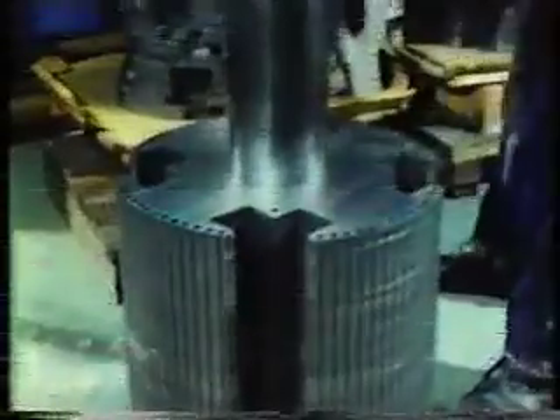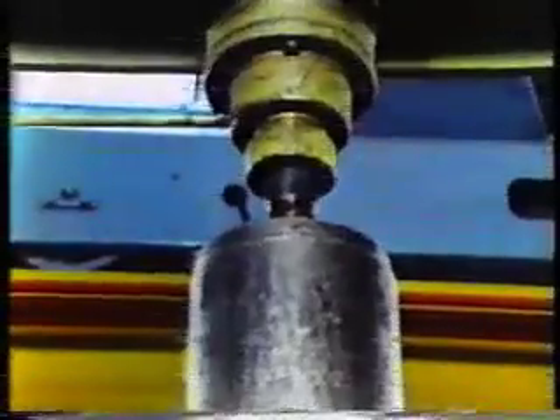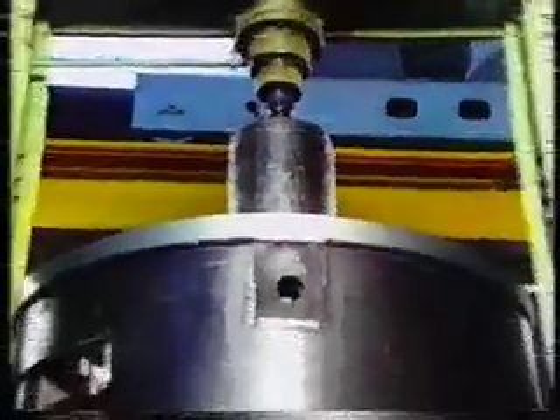Petbow themselves fabricate all the steel sections needed for every alternator. This machine automatically follows a drawn template to produce the various shapes required. A steel shaft is machined to a high degree of accuracy. It will carry the rotor assembly. The laminations are added and held between end plates. After compression, they're welded up to produce a solid core assembly. Laminations are also built up inside the bore of the stator frame. They too are hydraulically compressed and welded up, ready for the stator windings to be added.